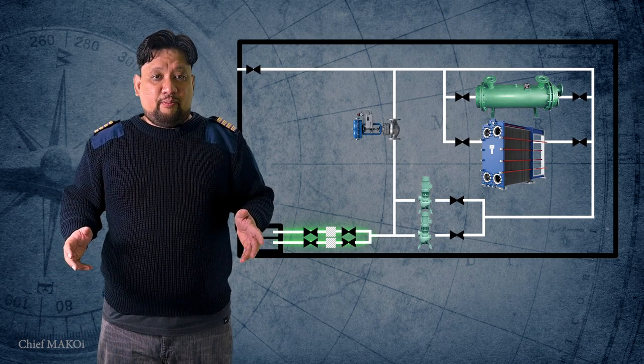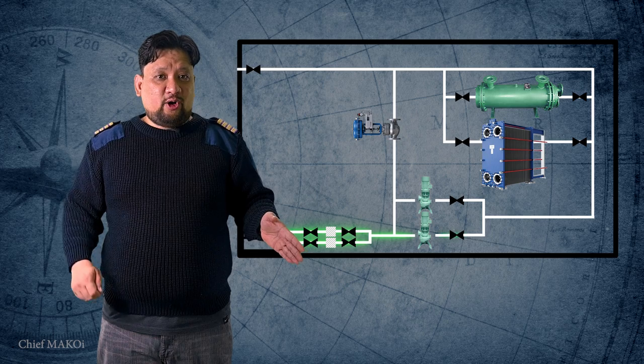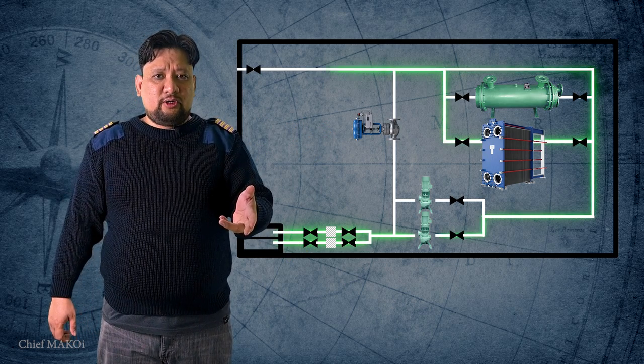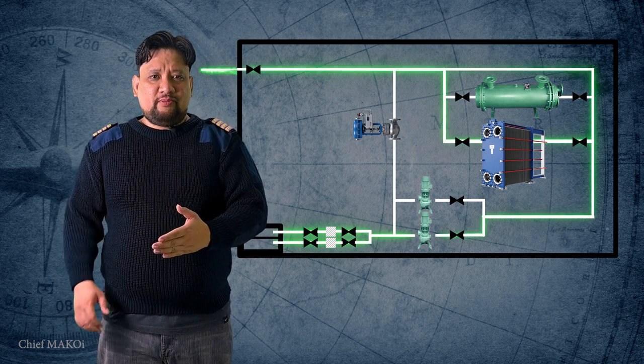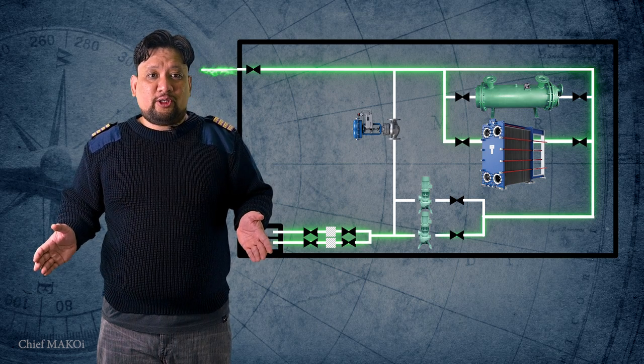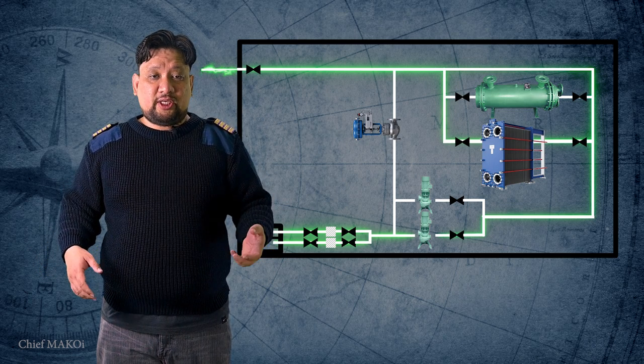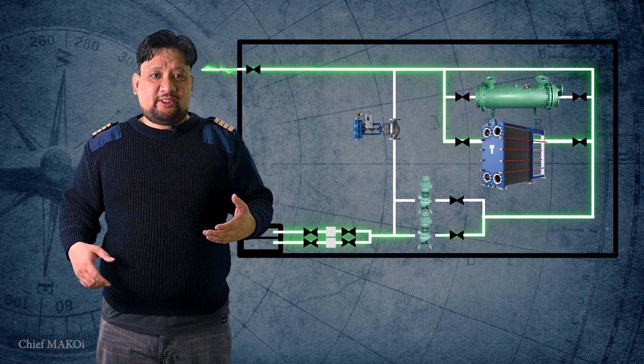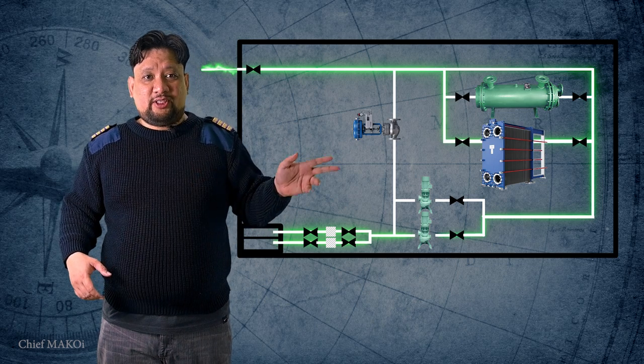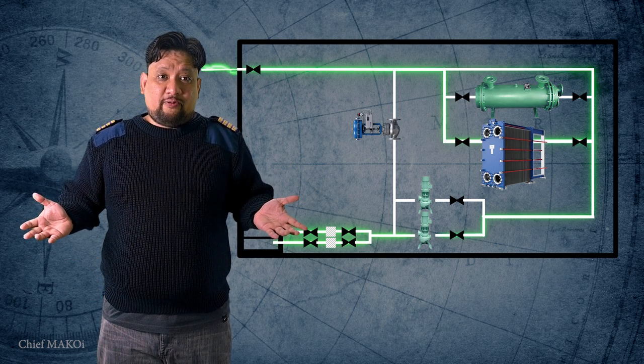meaning from the main seawater pump, it'll go through the lube oil cooler, the jacket water cooler, the main engine air cooler, and many other small coolers used in the various auxiliary machinery before it exits the system and goes back into the sea. Seems quite efficient, right?